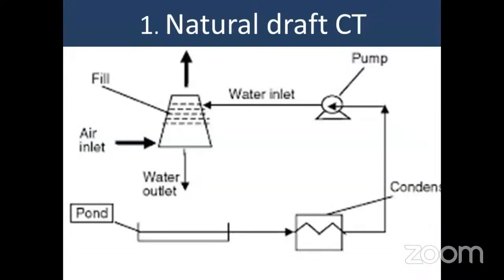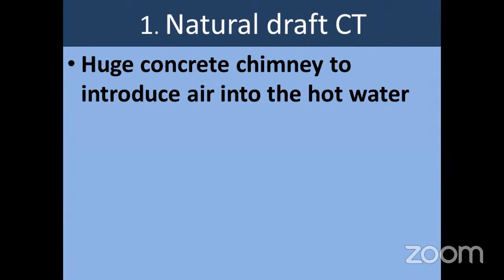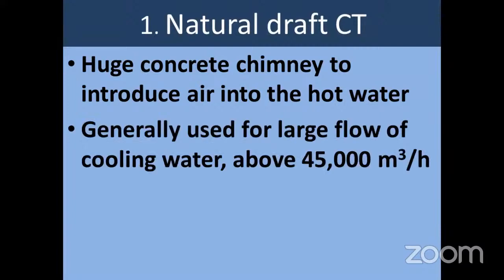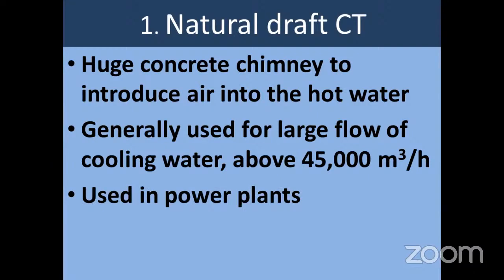Nowadays, as per the advice of MOEF, we are using natural draft cooling tower, in which the total energy consumption by the fan is avoided. Huge concrete chimney to introduce air into the hot water. Generally used for large flow of cooling water, that is above 45,000 meter cube per hour. It is happening only in power plants, sir. Nowhere else. The natural draft cooling tower, colloquially we call it as NDCT. In the book, anywhere I did not find that word NDCT. NDCT is found in the MOEF documents and all. NDCT means natural draft cooling tower.